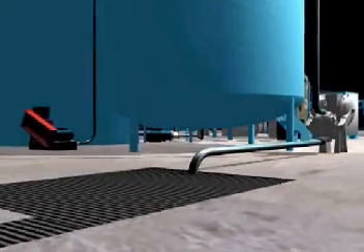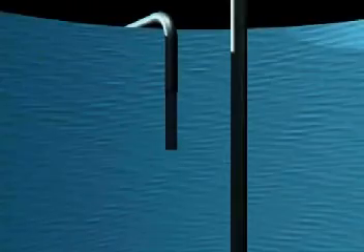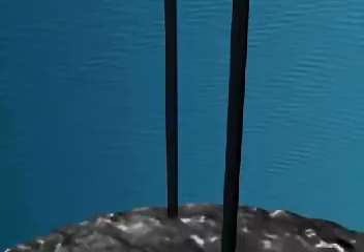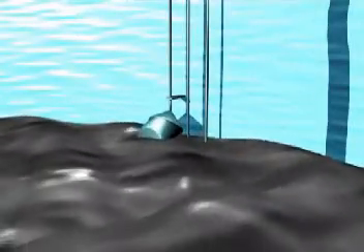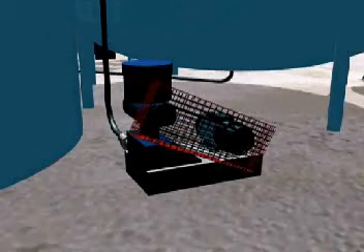Wastewater generated in the plant flows through collection trenches and receiving pits, from where it is pumped to a collection tank called the equalization tank. The equalization tank is equipped with float level sensors that control the transfer pump to the treatment tank. To maintain the equalization tank homogeneous, an air sparge is used.